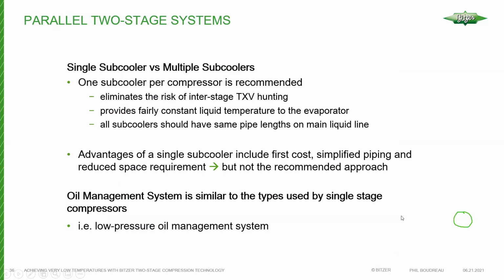Just taking a quick look at parallel operation. I'm going to flip through a couple of slides quickly here for the sake of time. Single subcooler versus multiple subcoolers. Generally, it's recommended to go with a single subcooler whenever possible when you're applying multiple compressors, because control can be very difficult. As your compressors stage down, you've got an oversized subcooler and you're trying to modulate that refrigerant while maintaining good superheat. That can be tricky to do. So wherever possible, use one subcooler per compressor, and that's generally the most robust approach.